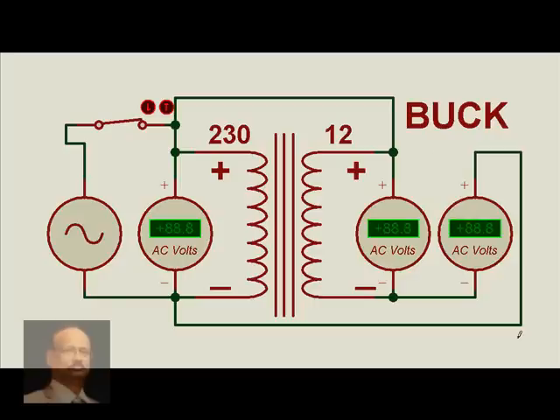So for voltage stabilizers, what we follow is that if our input voltage is increased by some reason, we try to buck the voltage by connecting in this fashion. Similarly, if the voltage is decreased for some reason, we try to boost the voltage by the other connection that we had seen. Now that is how we call a voltage stabilizer.